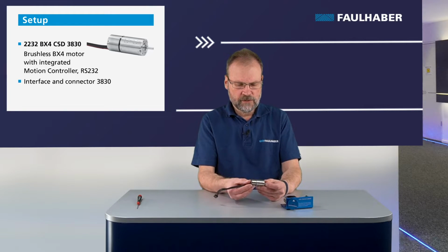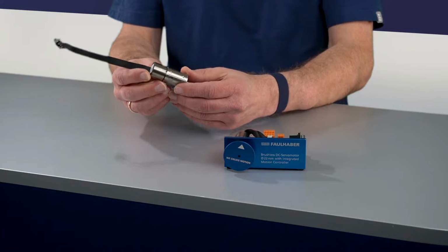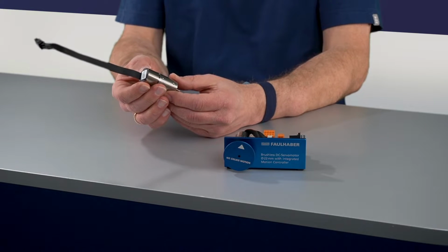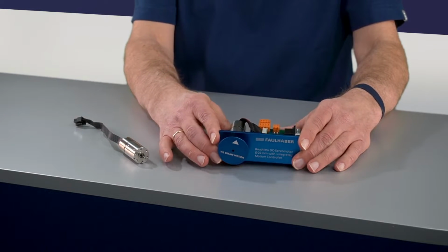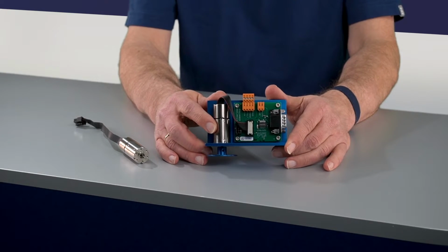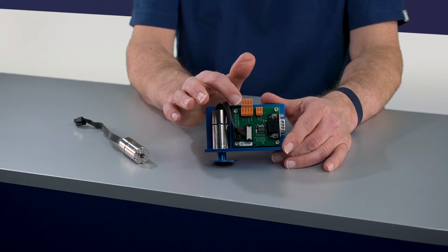The motor here is capable of generating roughly 16 millinewton meters of torque at a speed of 6000 RPM at nominal voltage of 12 volt here. Important to know, the complete drive electronic is integrated in the back here. For the video here, I'm going to use the integrated demo unit here. So there's the motor. And it's important to notice the adapter here is only for convenience.